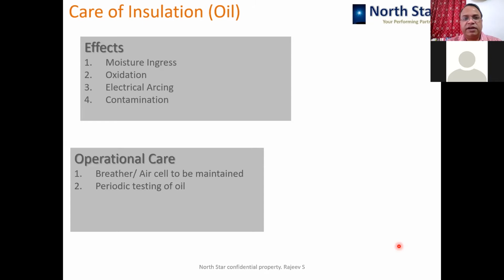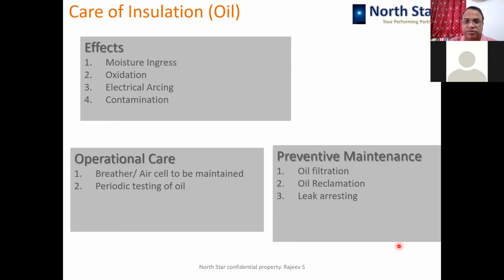But that doesn't mean that we should ignore it. Periodic testing of oil is required and has to be done. And as part of preventive maintenance, oil filtration, oil reclamation, and leak arresting have to be done, because leakages in transformers directly allow moisture to go inside the transformer. So leaks are not to be ignored and should be arrested in time.